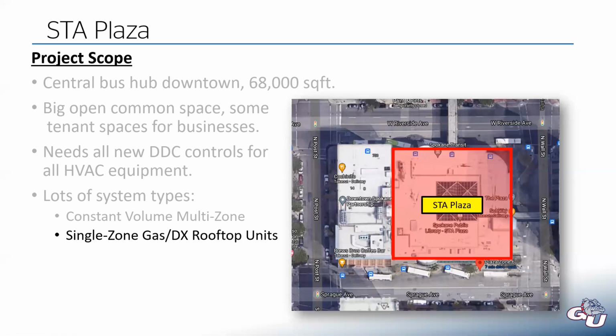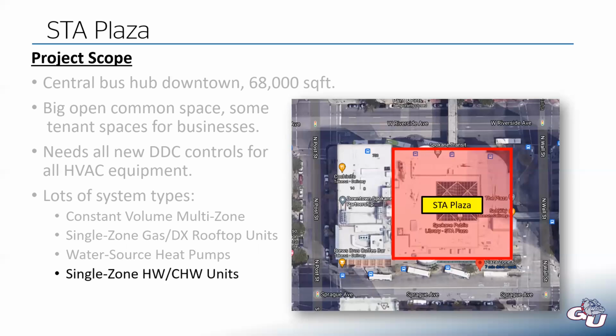But each one of those is a single zone unit, meaning that it just serves one tenant space on that floor. They had a handful of water source heat pumps and some single zone hot water and chilled water units, just some very small hot and chilled water air handling units that served some specific spaces, a hot and chilled water plant. So they had multiple boilers, hot water pumps, at least one chiller, and it was a water cooled chiller, meaning it's attached to a cooling tower up on the roof, which you can see right there. And the hot and chilled water plants are actually in the basement, meaning they had to pipe from the basement all the way to the roof to connect those pieces of equipment, and then cooling towers, which I talked about.